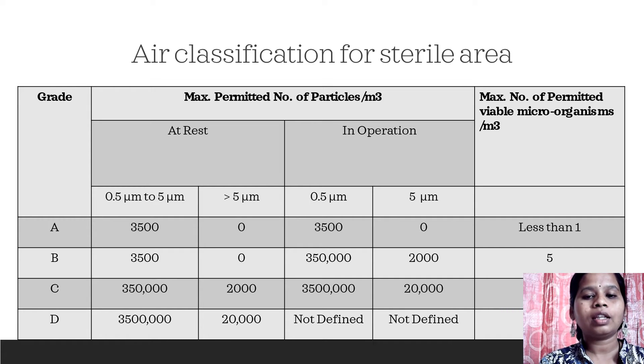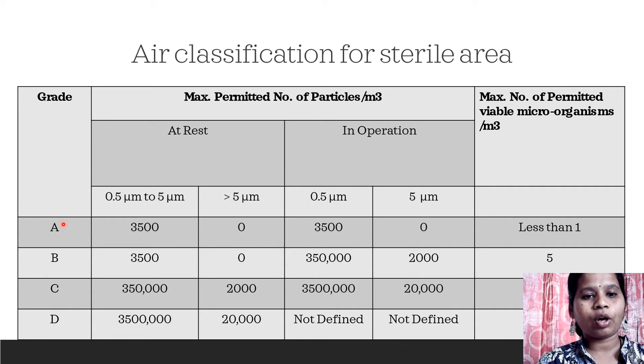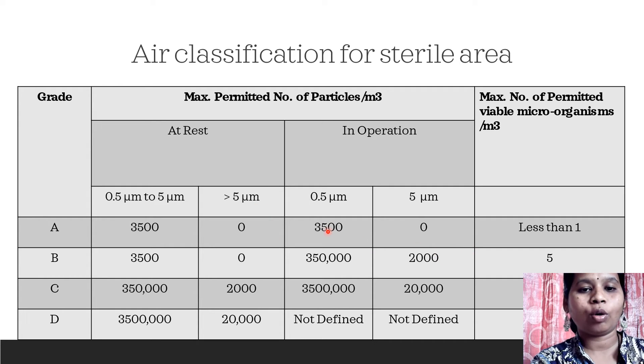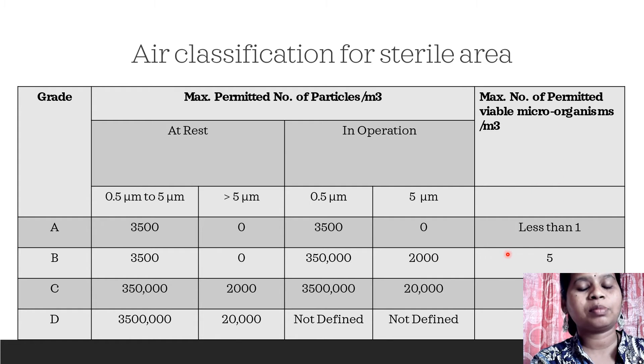Here we are going to see how many particles of what size are permitted in a particular area. For Grade A, which is considered for manufacturing of sterile products, particles ranging between 0.5 to 5 micrometers are permitted up to a count of 3500, and this same number is to be maintained in operation as well. More than 5 micrometer particles are not permitted at all. If the number of particles obtained in an area is less, then the maximum number of permitted viable microorganisms is also considered less.